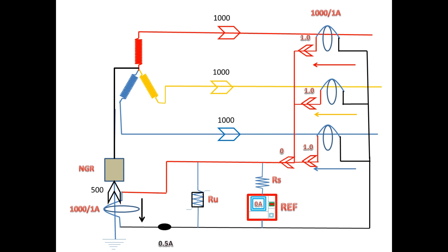Due to this, the sum of all three phase CTs will be 0 at the node. When the external current tries to flow through the core balance CT, it creates a high impedance path for the current entering from the neutral CT. So this neutral CT current will avoid this path and try to find another path.